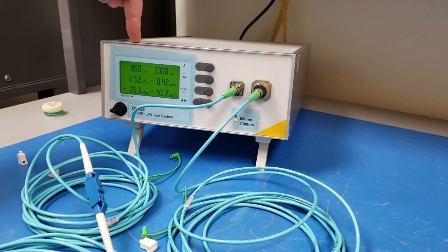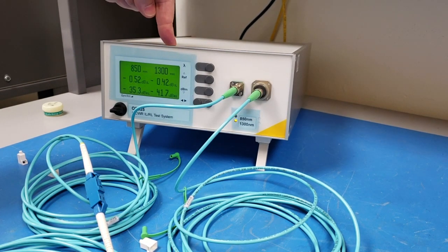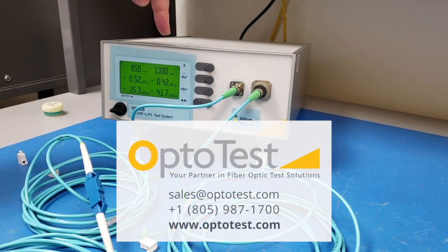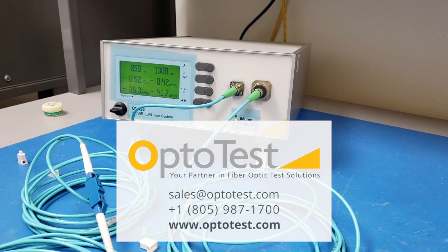So this cable is giving us a 0.52 dB insertion loss at 850, 0.42 dB at 1300, and a return loss of 35.3 and 41.7 for 850 and 1300.